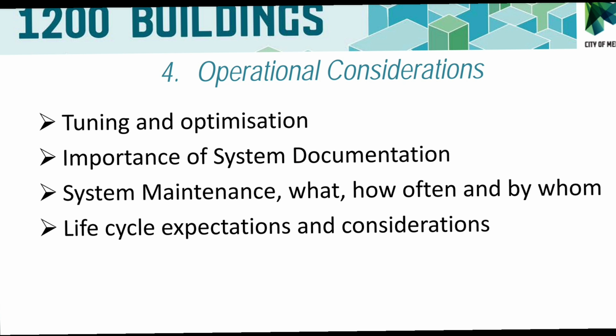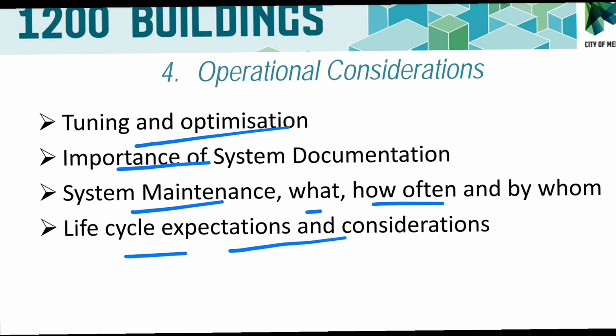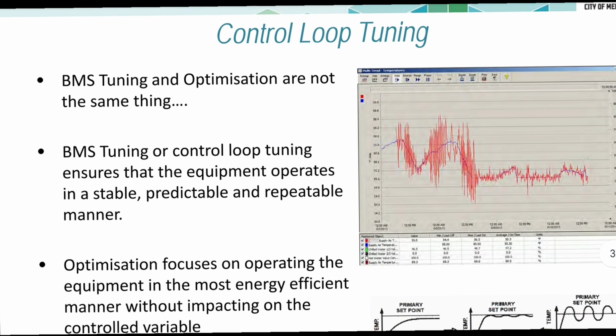operation considerations: tuning and optimization, importance of system documentation, system maintenance (what, how often and when), life cycle expectation and consideration. Okay, next is control loop tuning. BMS tuning and optimization are not the same thing. BMS tuning, or control loop tuning, ensures that the equipment operates in a stable, predictable and repeatable manner. Next, optimization focuses on operating the equipment in the most energy efficient manner without impacting the control variables. The first stage of optimization includes BMS loop tuning.